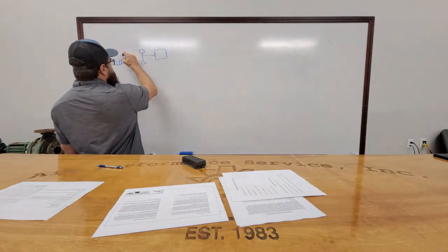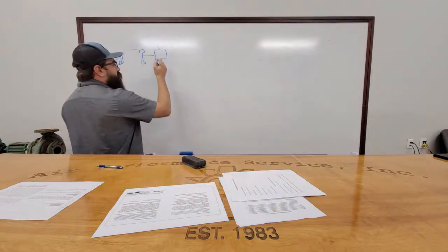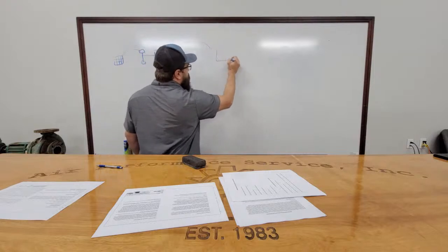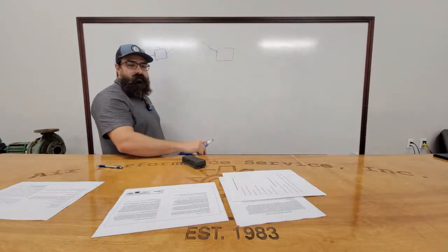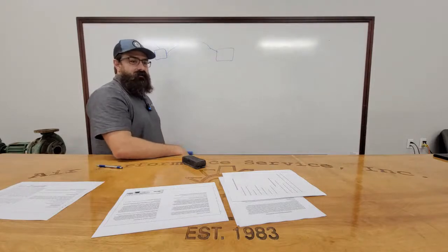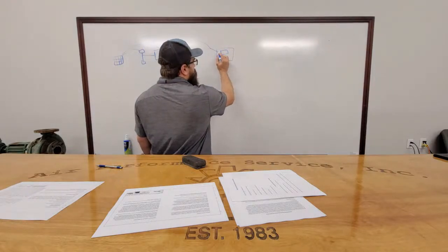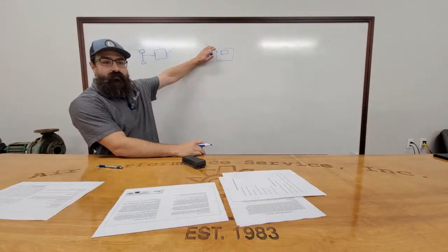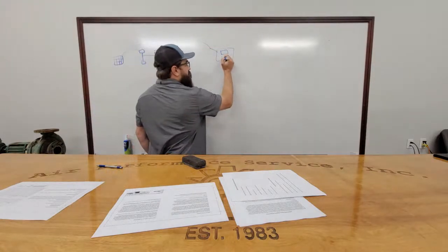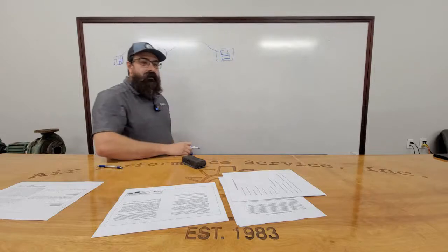This schedule is telling this equipment to start. Once this equipment starts, it's going to tell our central plant over here that, hey, I have a request for cooling. I need a chiller. So then a chiller is going to start up. Well, on startup, we give this chiller X amount of time to get the loop down before we bring on our lag chiller, right?